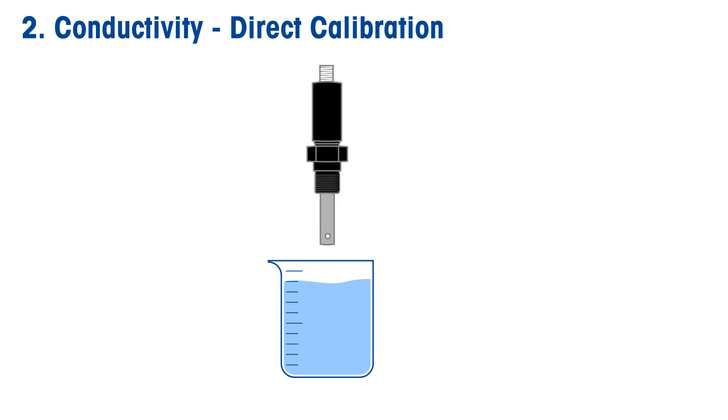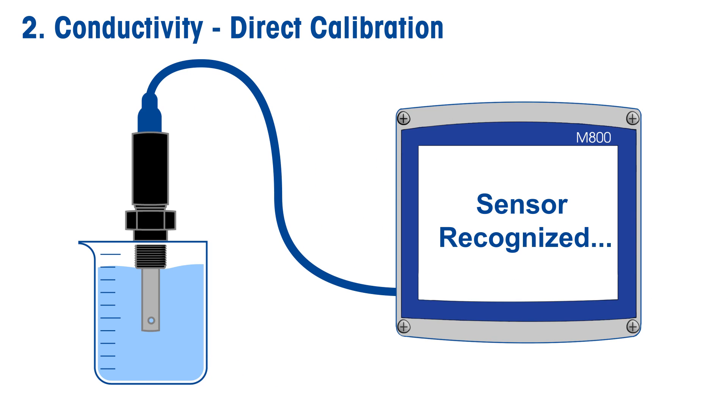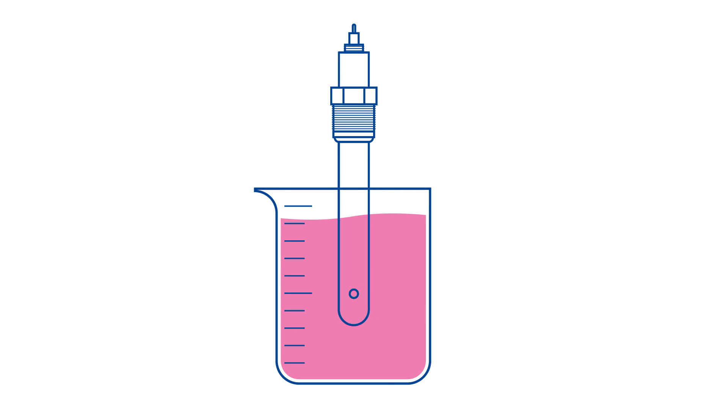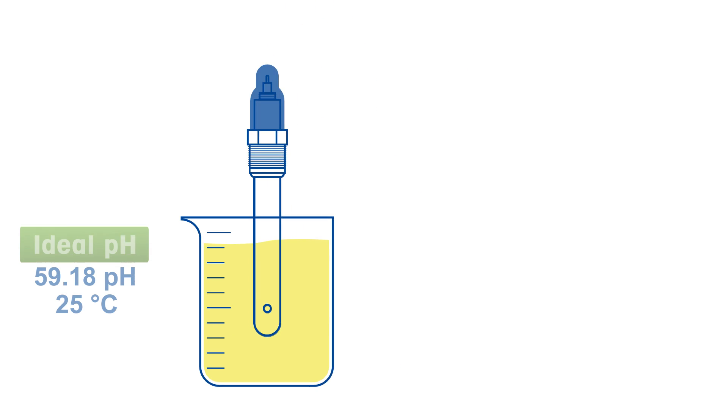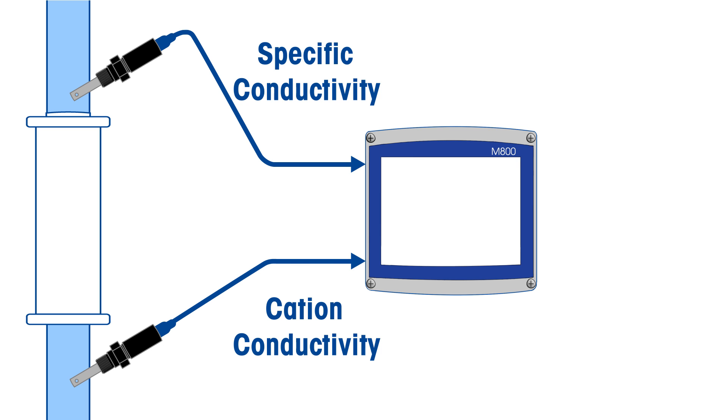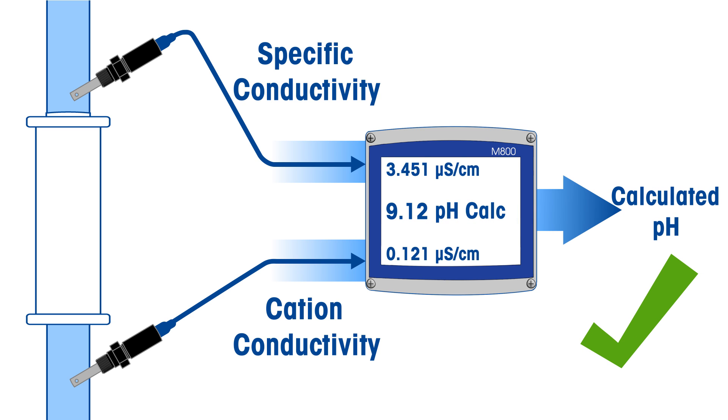Second, conductivity sensors can be directly calibrated with minimal introduction of error. All pH reference electrodes have a variable junction or diaphragm potential that can change between buffer calibration and process measurement, introducing some uncertainty to subsequent measurements. This makes calculated pH based on conductivity significantly more accurate.